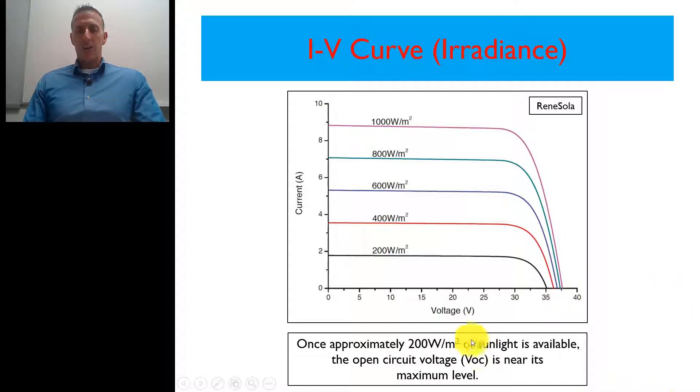What we're saying here is that once approximately we get 200 watts per meter squared of sunlight that's available, that open circuit voltage, the VOC, which is right here, it's the maximum voltage that module puts out, it is going to be near its maximum level.